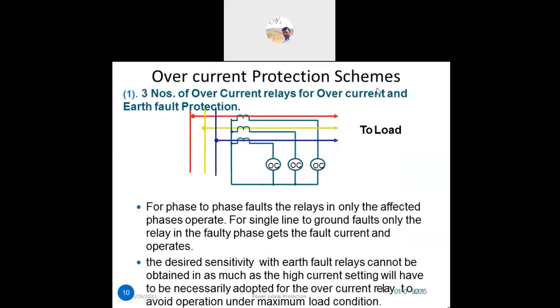Now let's see the overcurrent protection schemes. The first scheme uses three overcurrent relays for overcurrent and earth fault protection — one relay per phase. For phase-to-phase faults, only the relay in the affected phase operates.